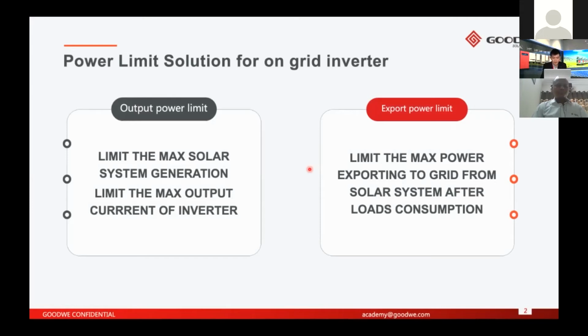As you know, because of different applications and different requirements, what is the power limit? On our side, we split the power limit into two parts: output power limit and export power limit. If you just want to limit the inverter output power, it's output power limit, and in this case there is no load consumption in the system. But if you have load consumption in the system and you also want to limit the power to the grid, that's the export power limit.